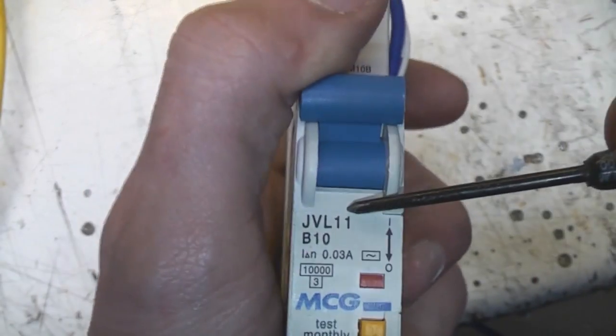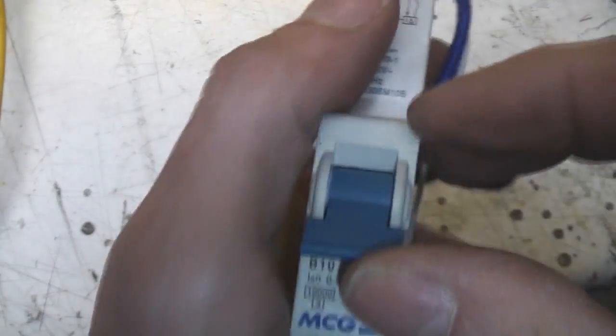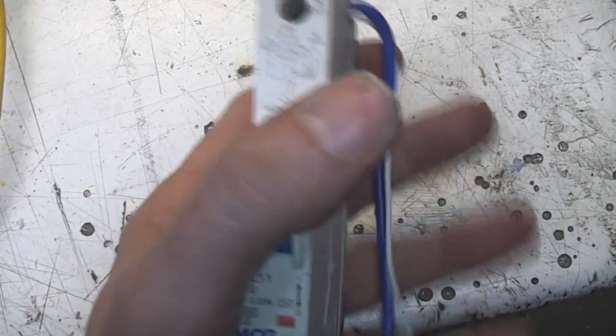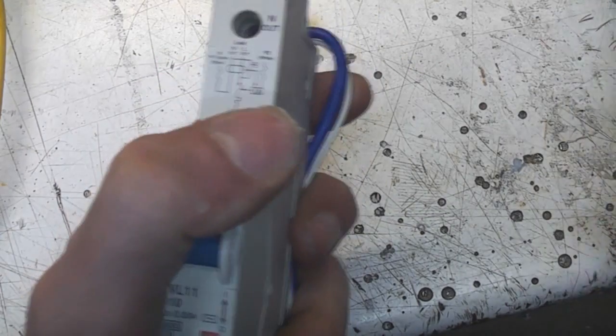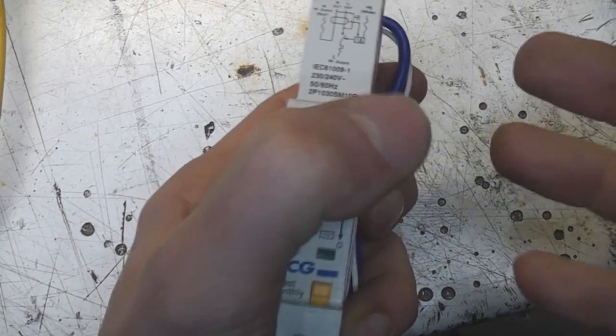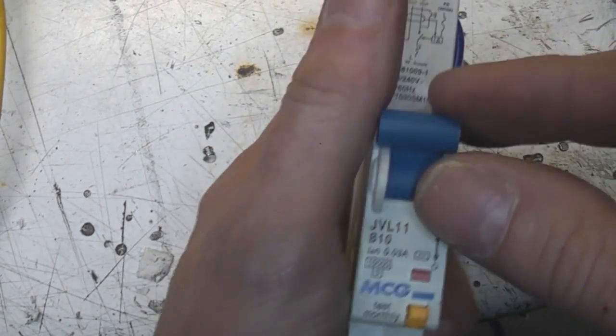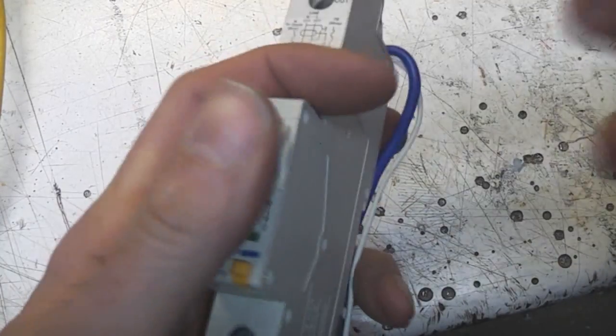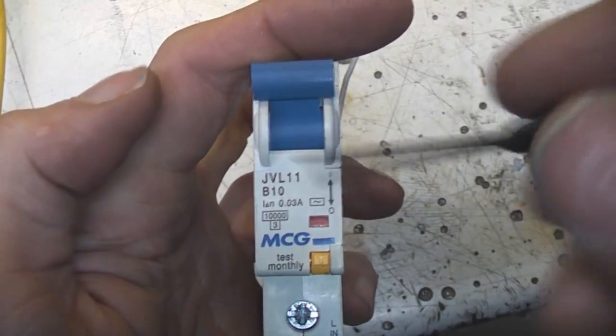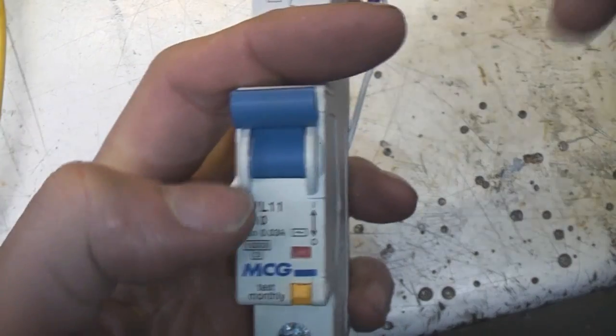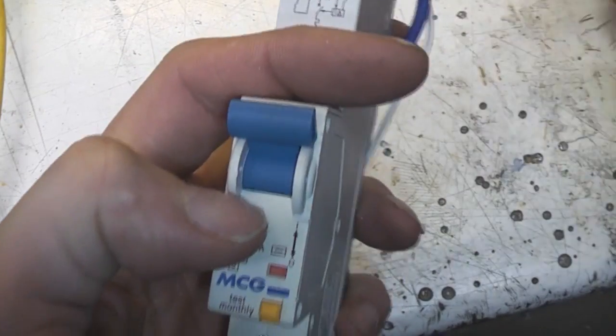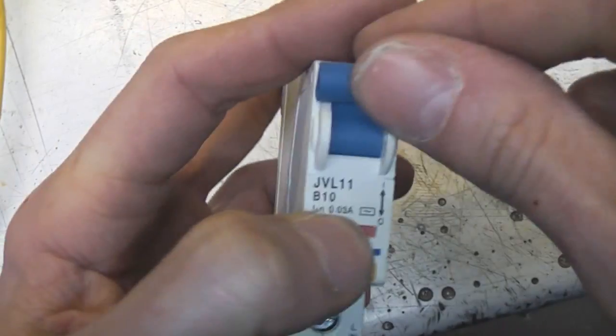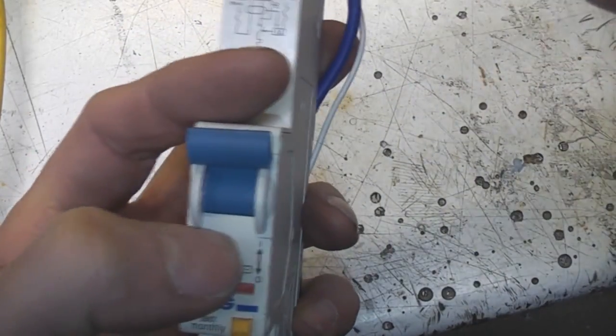One reason why this is quite important is that the main purpose of a circuit breaker is to protect the wiring. So let's say you have a massive great switch mode power supply, or more often a lot of small switch mode power supplies, which because of their input capacitor produce a fairly large current surge when you turn them on. One solution you might think is, well, we'll just put in a higher rated breaker. The problem is that if we've got a 10 amp breaker, then our downstream wiring is rated for 10 amps. If we put in a 20 amp breaker, we'd have to uprate all our wiring so that it could withstand 20 amps, because that's the purpose of the breaker.